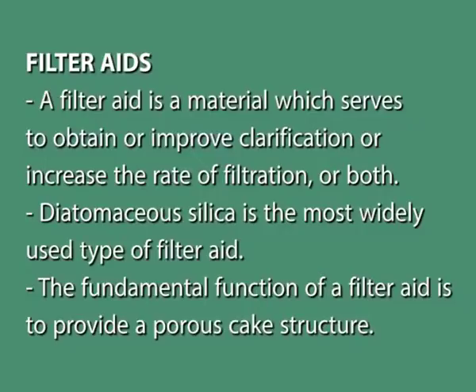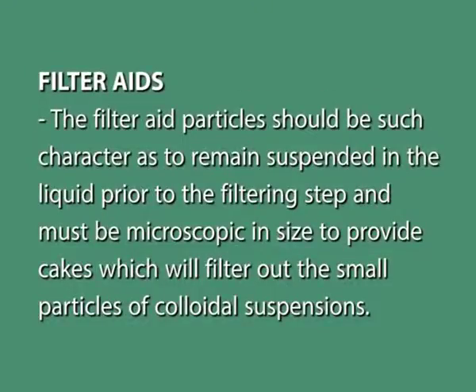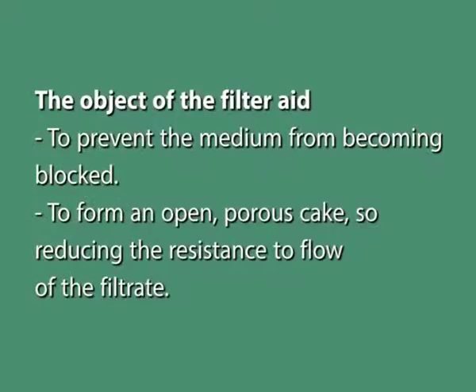The fundamental function of the filter aid is to provide a porous cake structure, built up simultaneously with the deposition or retention of the suspended particles. The particles of filter aid must form a rigid skeleton or lattice structure which is capable of entraining the gelatinous or fine particles of unfiltered liquid, yet leave channels in the filter cake through which the pure liquid may pass at a rate and under pressure differentials that are practical economically. The object of the filter aid is to prevent the medium from becoming blocked and to form an open porous cake, reducing the resistance to flow.